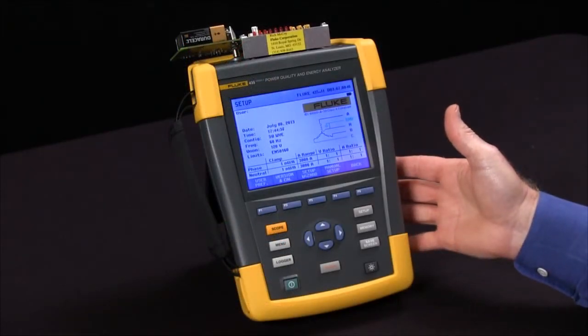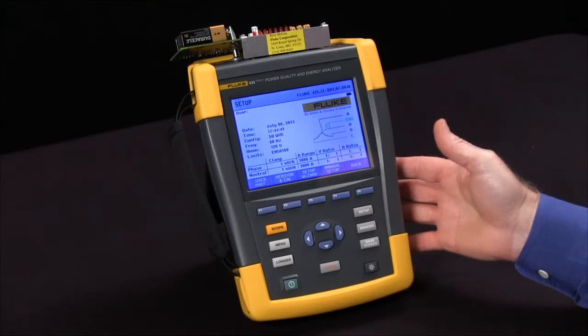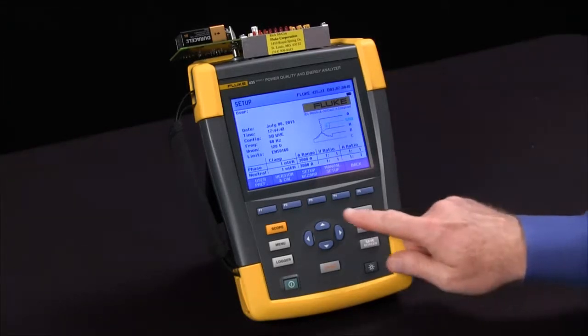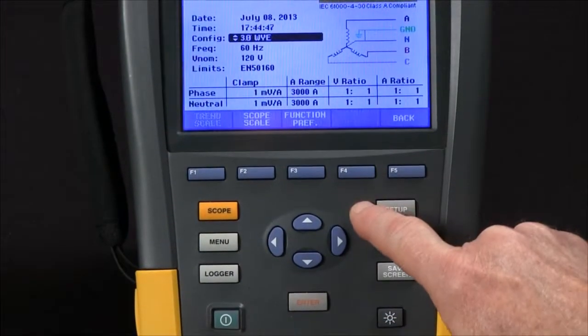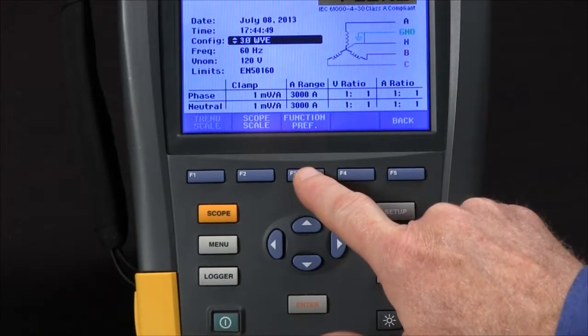In this video we're going to talk about how to set up the 435 to measure dips and swells. From our setup screen we're going to start off by going to manual setup with F4 and then F3 for function preference.